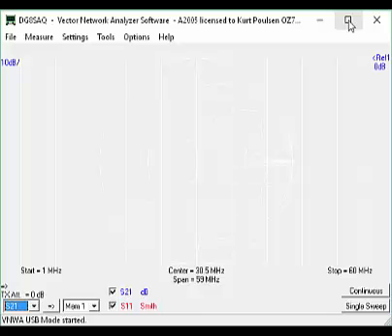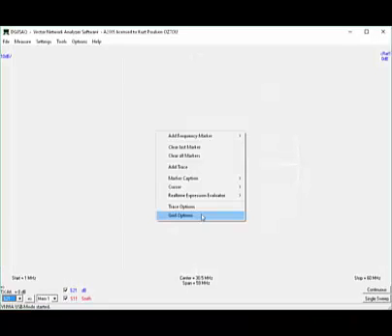These are the default settings, as span from 1 to 60 megahertz, and only two traces selected, S11 Smith and S21 in decibel notation. You may change to full screen by clicking as the green arrows indicate. On most computers, it is hard to see the grid lines in the Smith charts, so we have to do some specific settings to get these lines clearly visible.